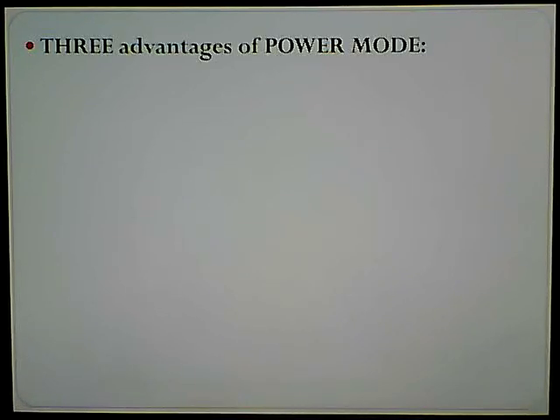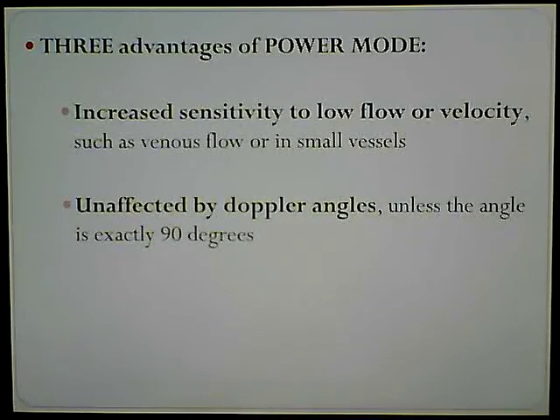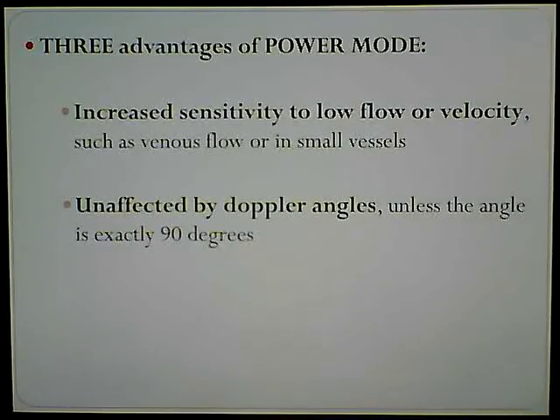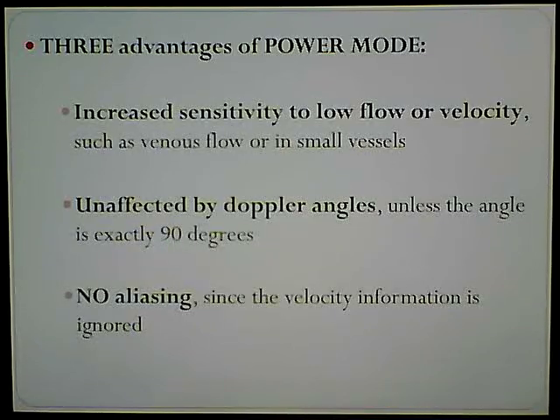There are three advantages of power mode. First, increased sensitivity to low flow or velocity, such as venous flow or in very small vessels where color flow is having a hard time. Second, it is unaffected by Doppler angles unless the angle is exactly 90 degrees - it doesn't matter how you're holding that probe. Third, there is absolutely no aliasing. Why? Because there's no velocity information - the velocity information is ignored.